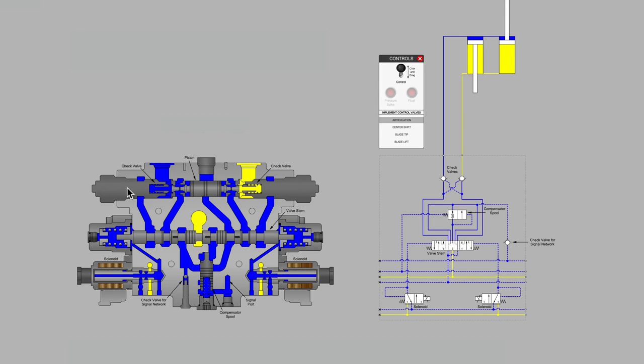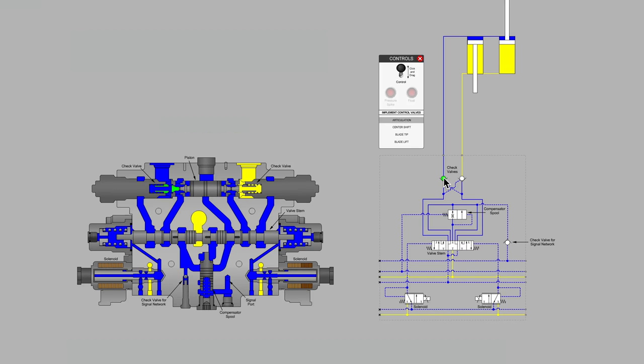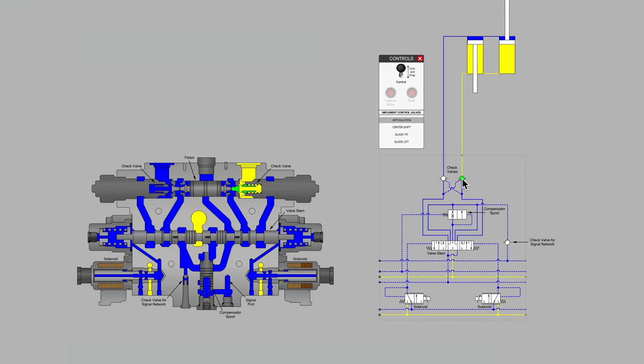But if you were in position to remove this cartridge and hold it in your hand, then all of a sudden you might find that pushing on this poppet on the end, there's a spring behind it and a fairly lightly weighted spring. And then you look at the schematic and you say, hey, I don't see the spring there. That little zigzag pattern that would usually be the spring. It would be right there and there would be one on this side. But in this machine, it's a lightweight spring and the manufacturer chose to leave it out. That's their choice.